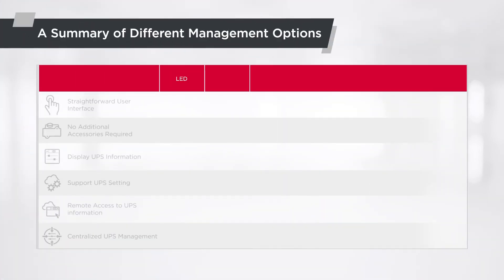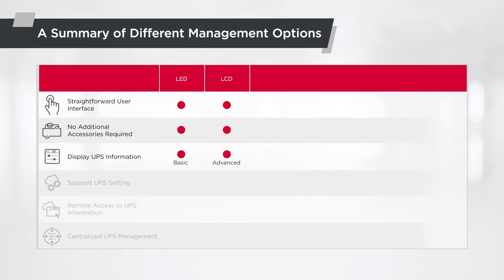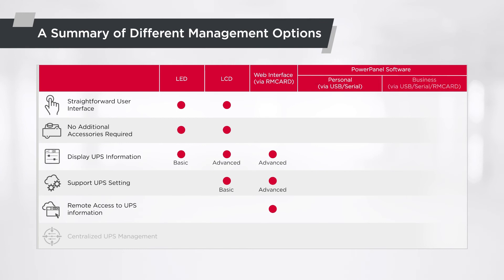For managing through LED indicators and LCD display, the operation interface is straightforward and there is no need to install additional accessories on the UPS to learn the power information. The LCD display can also allow UPS settings. Through the RM card web interface, it shows power information, supports UPS settings, and enables remote monitoring. With PowerPanel software, both Personal and Business are able to display UPS information and perform UPS settings. Additionally, PowerPanel Business also allows users to get UPS information remotely and monitor multiple devices through a single interface to achieve centralized management.